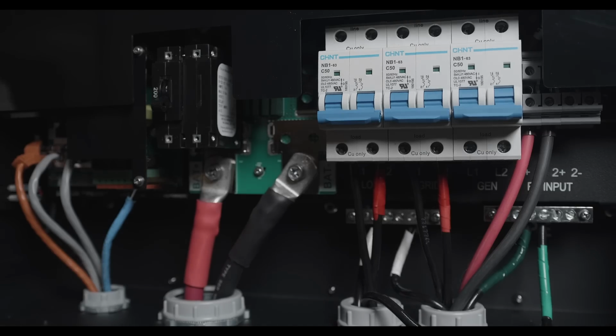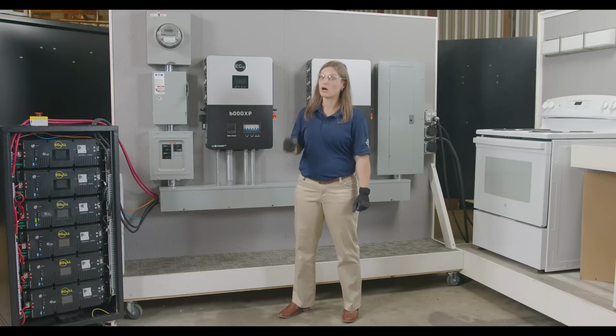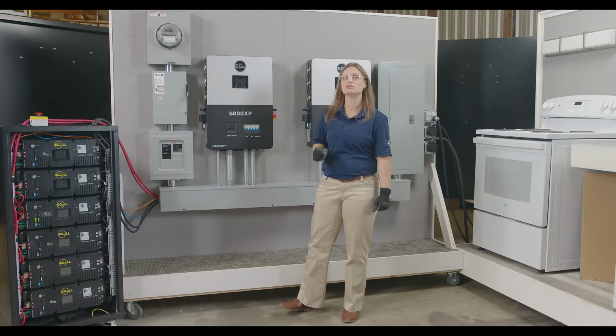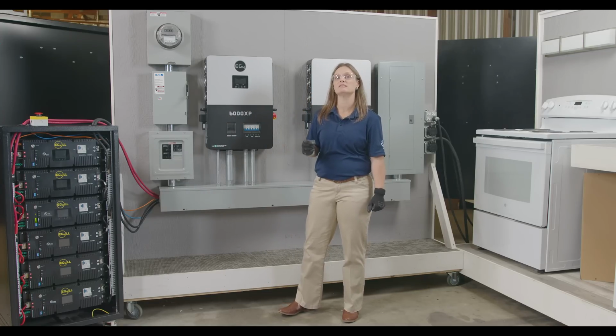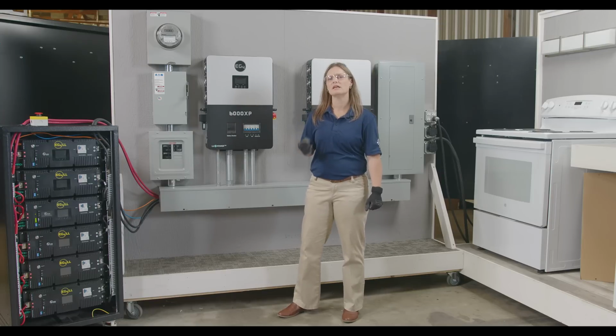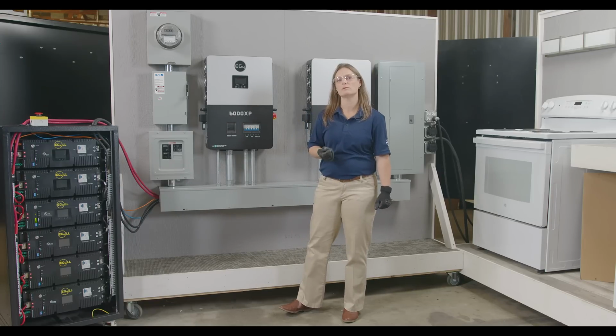Now we want to double check our wiring. Make sure all power and communication cables are correctly wired. Verify your dip switch settings according to your battery manufacturer specifications. Always keep safety first. Be sure to follow the inverter startup and shutdown procedures outlined in section 12 of your manual. Let's quickly go through the startup sequence.